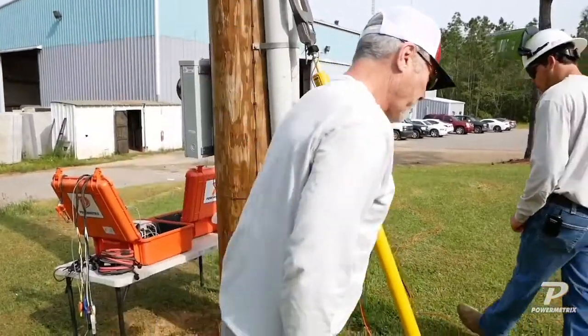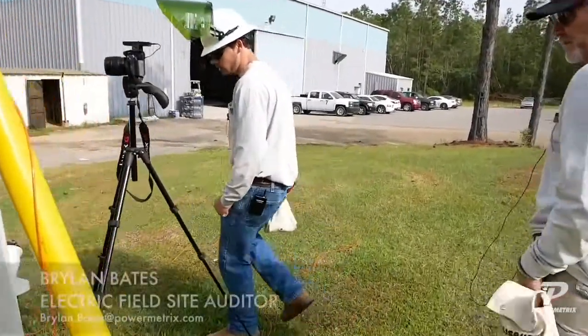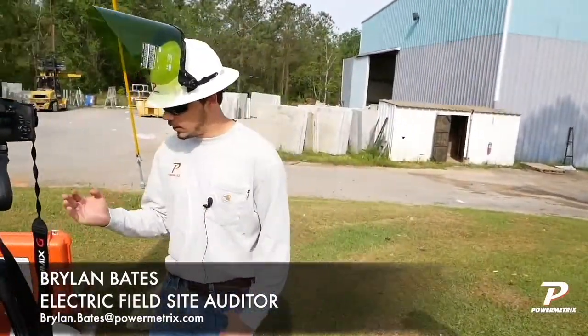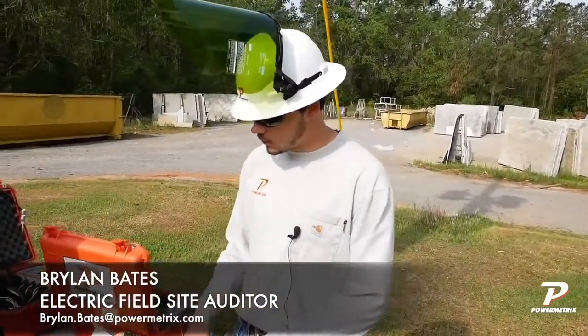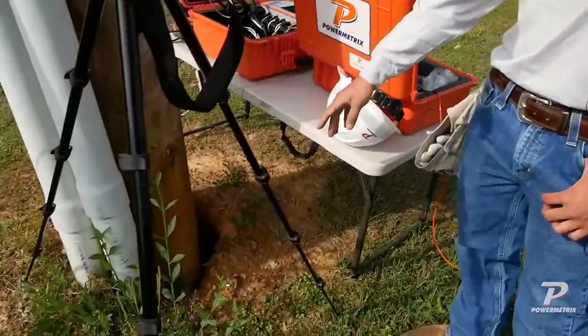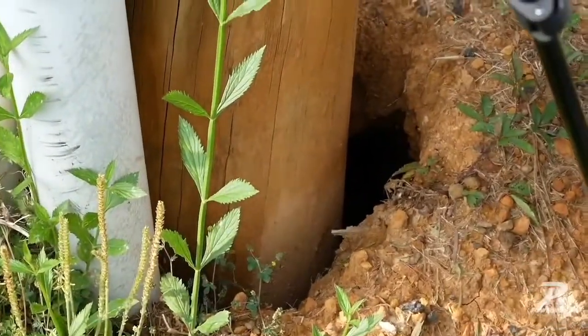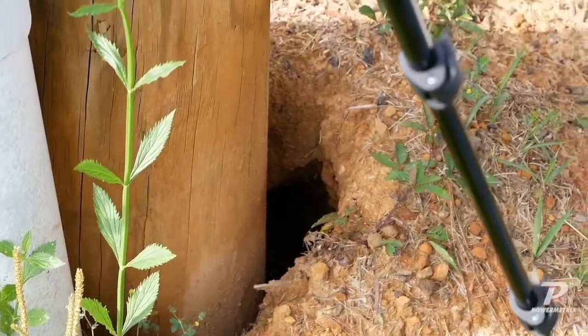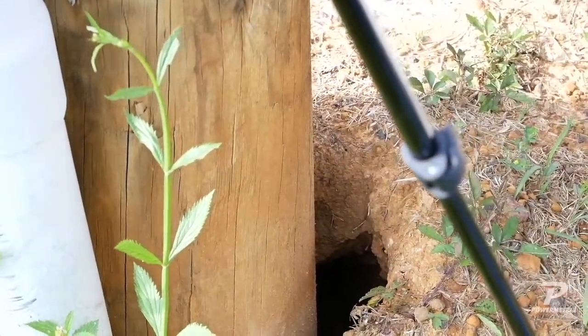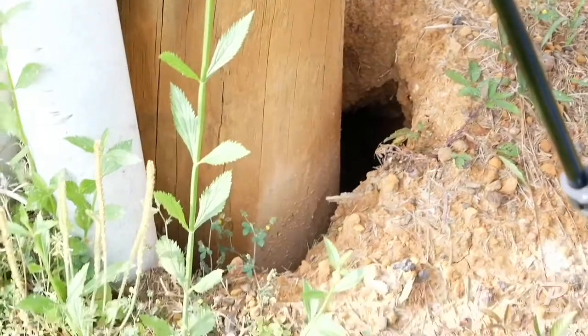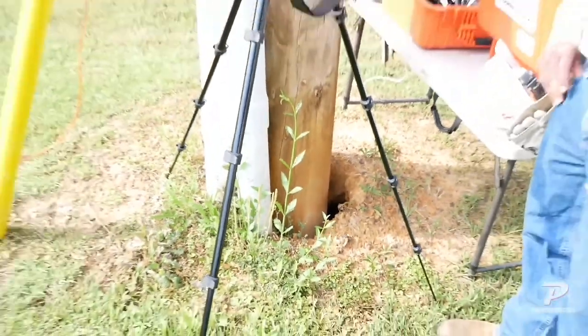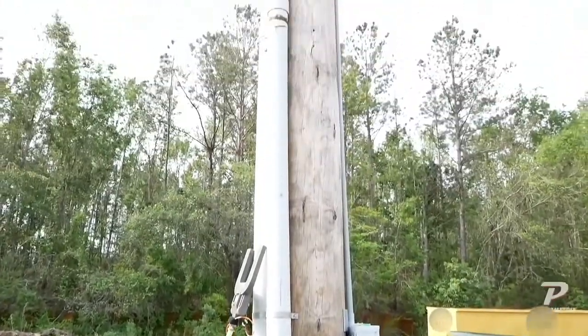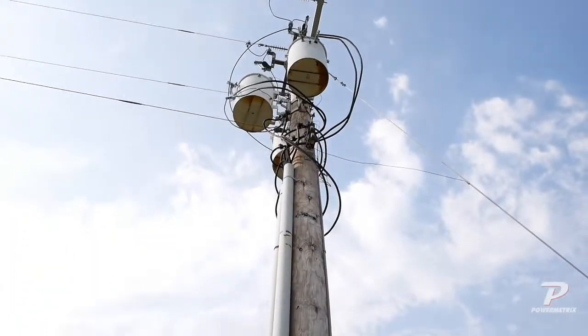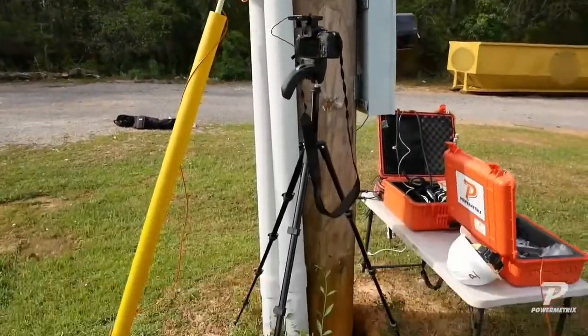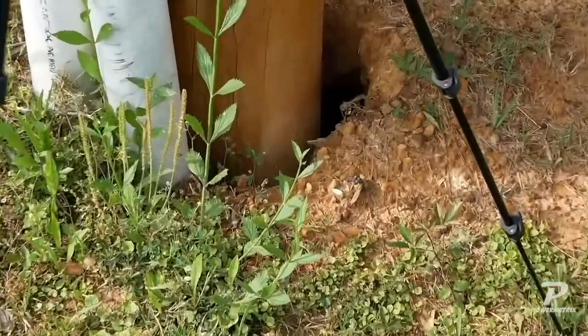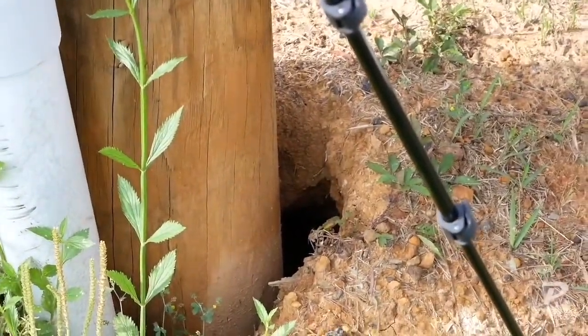But we did note one thing at the base of the pole. Like we've talked about in previous videos regarding the pole leaning or the ground settling, you can see in this video where the dirt has settled and the pole is actually beginning to lean. You need to make a note of that so the utility can come in and refill it, put foam in it, or however they want to handle it, because once something like that starts, it doesn't tend to get any better - it'll start getting some washout action under there.